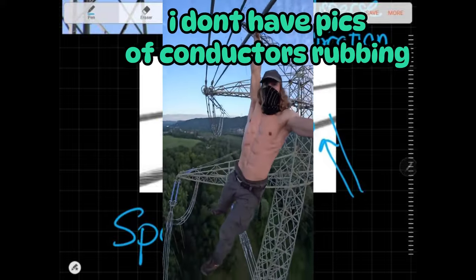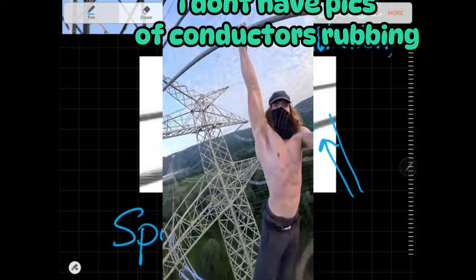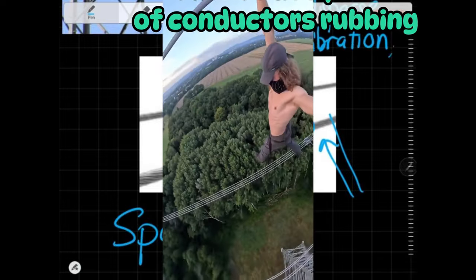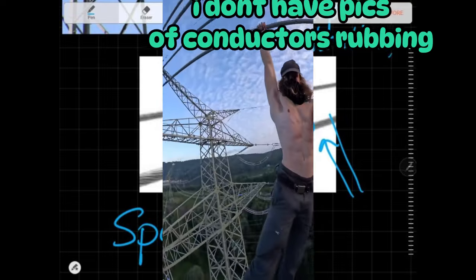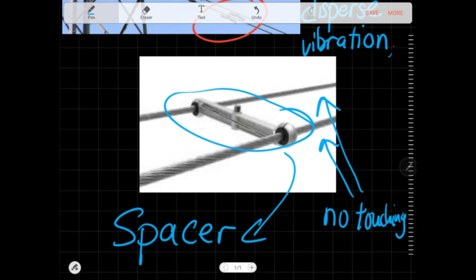You can guess how wild the cost savings they think that they were going to achieve. But having bundles close to each other may cause rubbing and scratching. The friction from rubbing may deteriorate the strands and the bare current carrying conductors. So, there is where spacers come in, to keep the lines parallel and not making contact with each other. No contact, no friction. No friction, no fire.